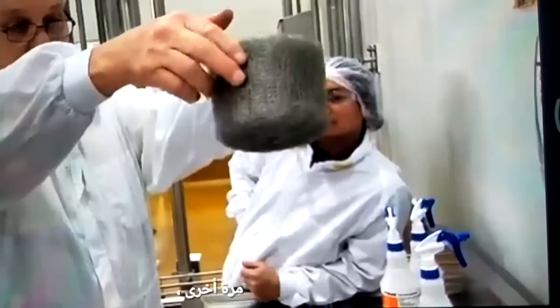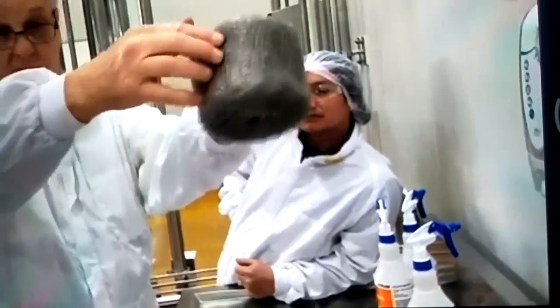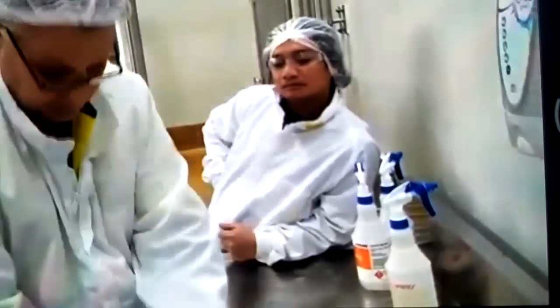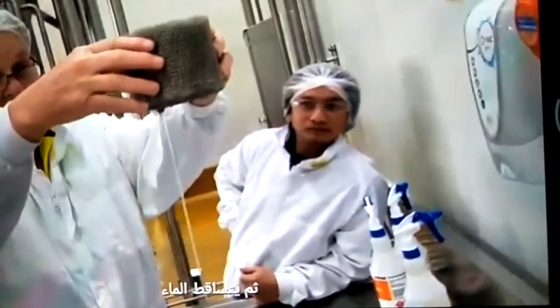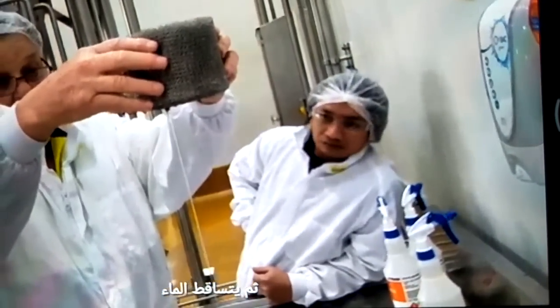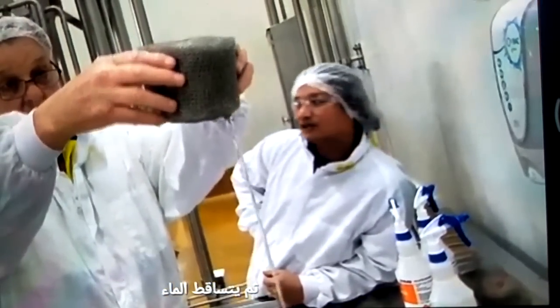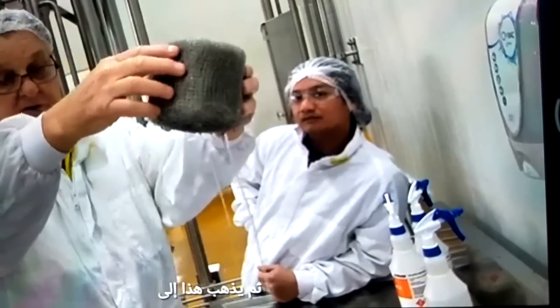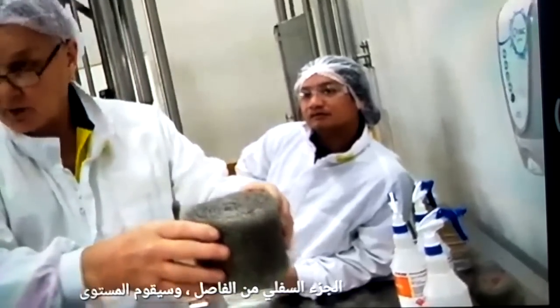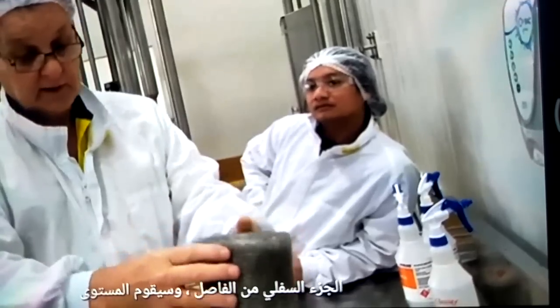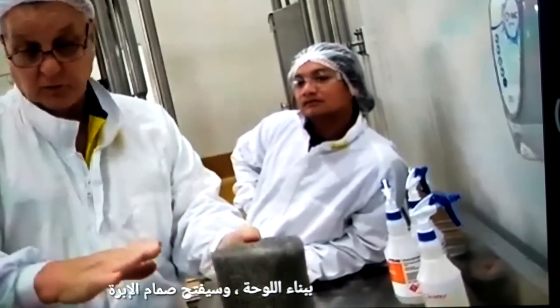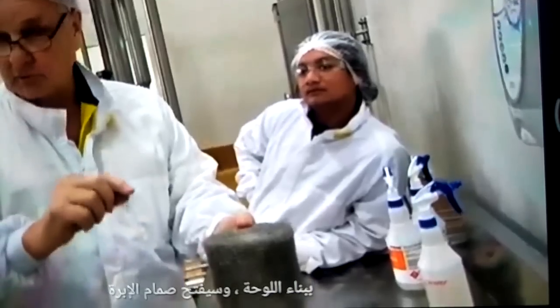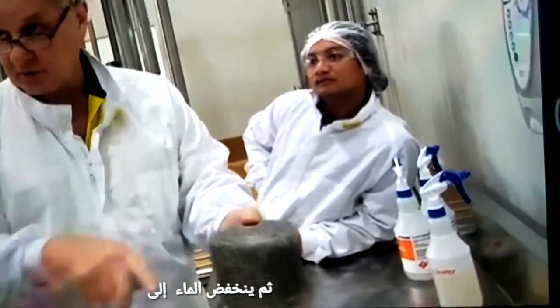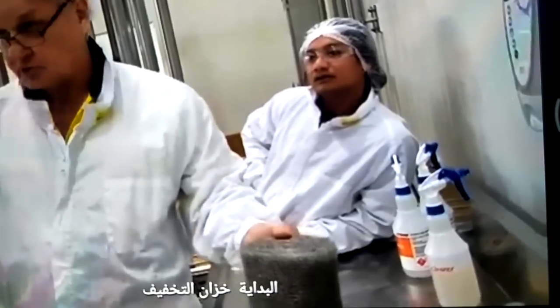See how it holds water, okay? So when it holds water, water will come in, then water will then drip out. And then this goes to the bottom of the separator. The level will build up, the float will come up, the needle valve will open, and then the water goes down to the dilution tank.